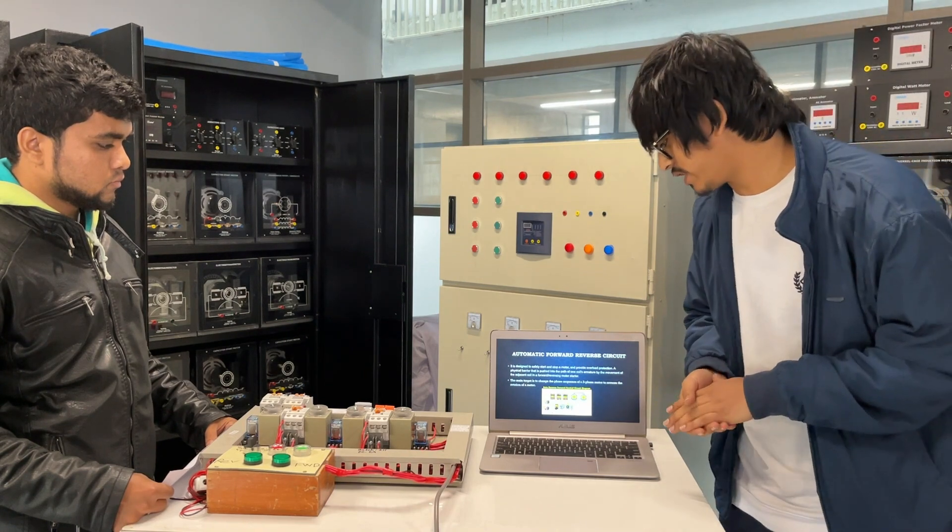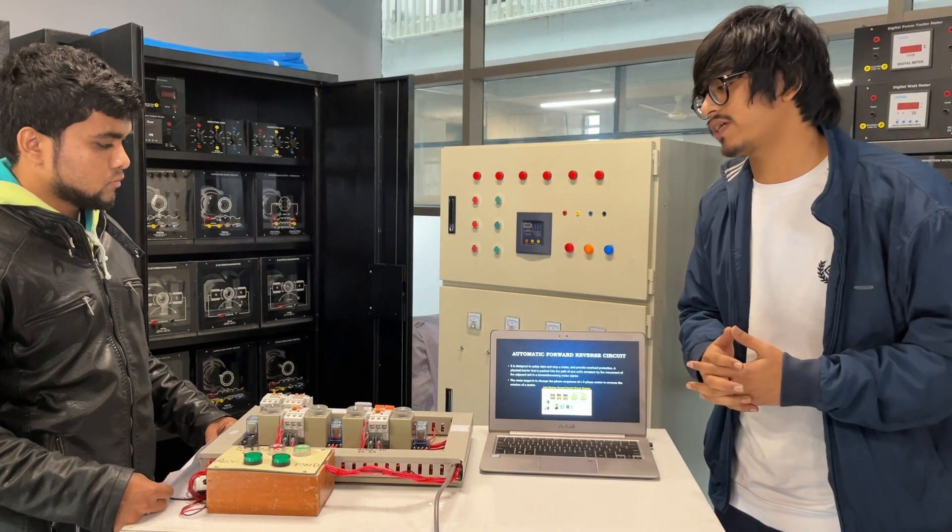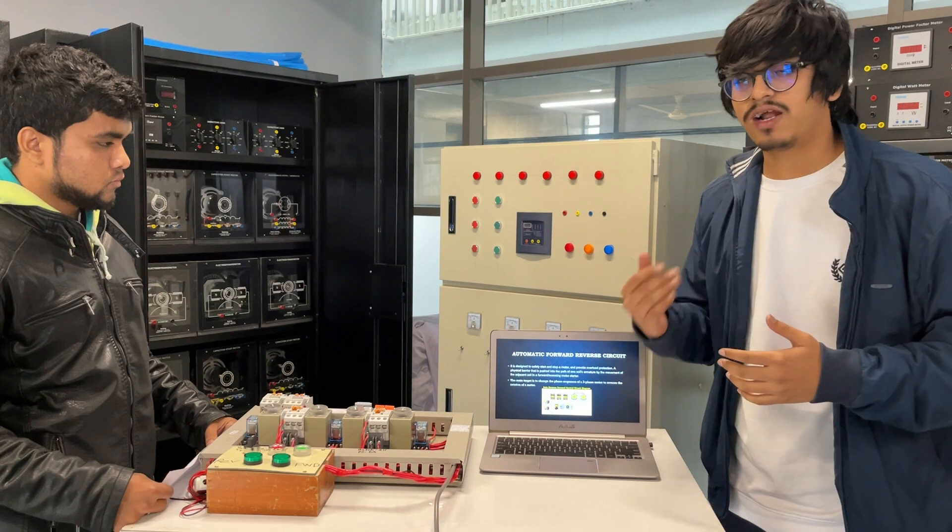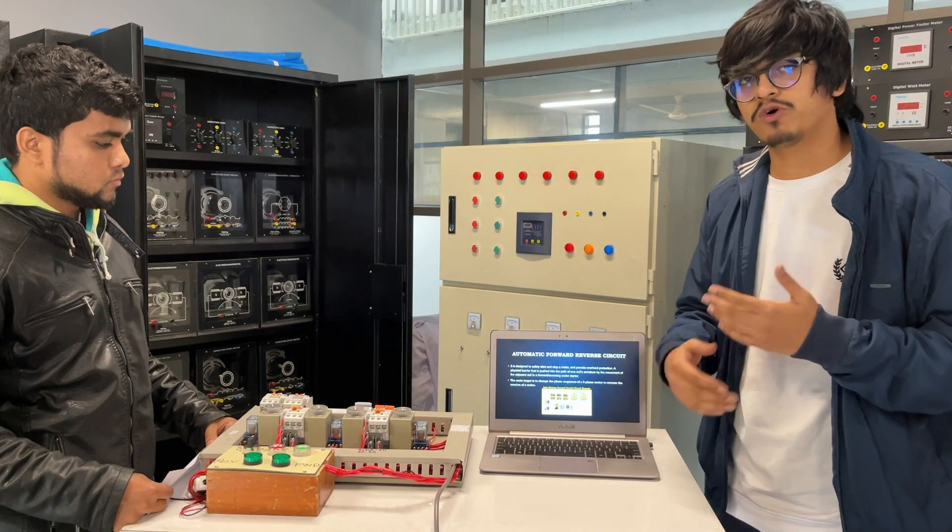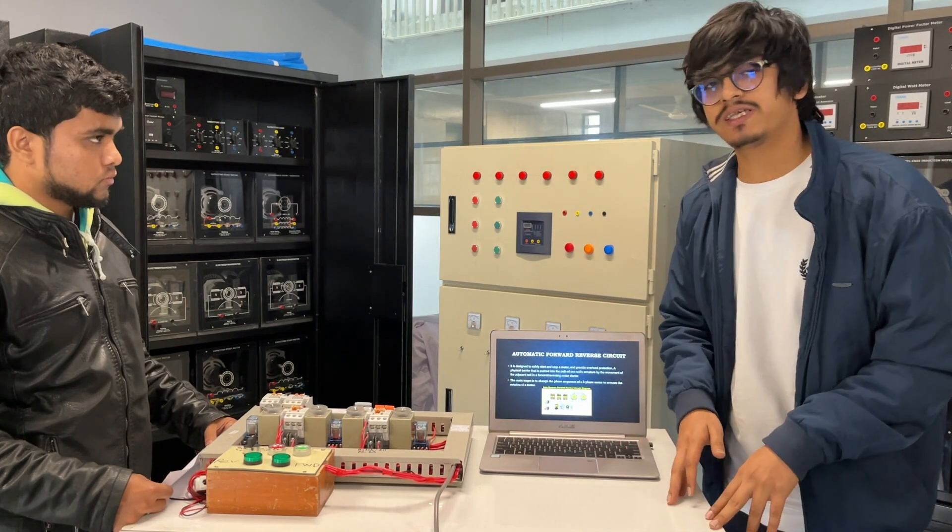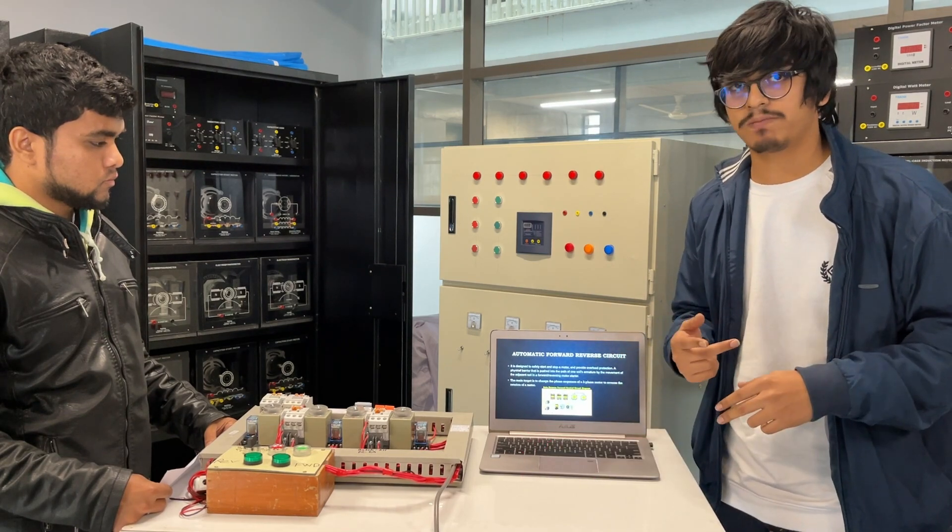Here is the automatic forward reverse circuit. So what does an automatic forward reverse circuit do? An automatic forward reverse circuit basically runs a motor in both directions. The basic principle is that in a three-phase motor when we are using forward, the phase sequence is RYB. In reverse we will be using RBY or BYR. Basically we will swap two phases.